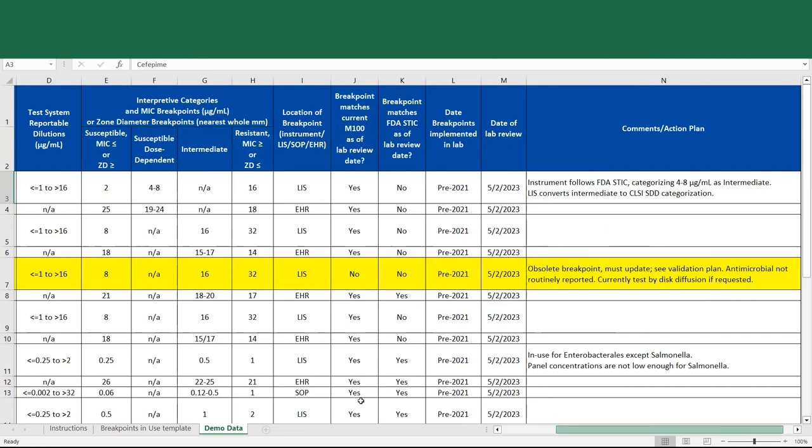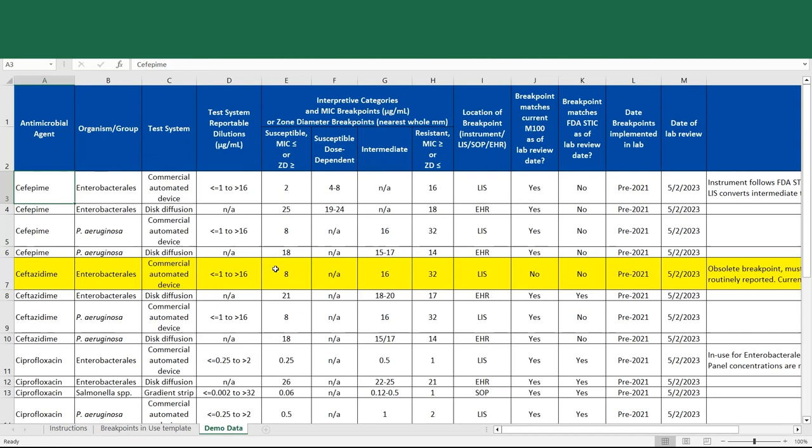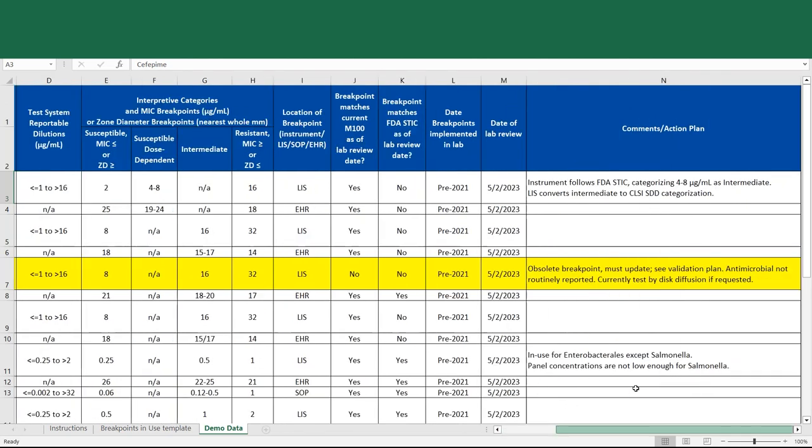In the case of ceftazidime, we see that the breakpoints are less than or equal to 8, 16, and greater than or equal to 32, and that these do not match current CLSI breakpoints, and they do not match current FDA breakpoints. So in the comments column, it's acknowledged that this is an obsolete breakpoint and must be updated, and that there is a validation plan.